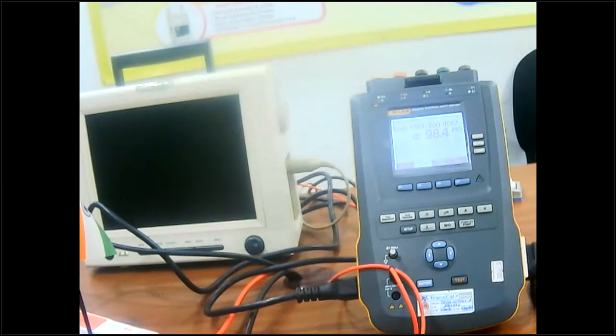Jerry: So the standard describes for us that we should use for the touch current test a conductive but non-earthed, non-grounded test point on the medical device where the patient would be likely to touch it or the caregiver would be likely to touch it. Well, here's a little bit of a problem. An awful lot of medical devices today, including patient monitors, do not have any conductive test point where the patient could touch it. There just aren't any, earthed or not earthed, grounded or not grounded.